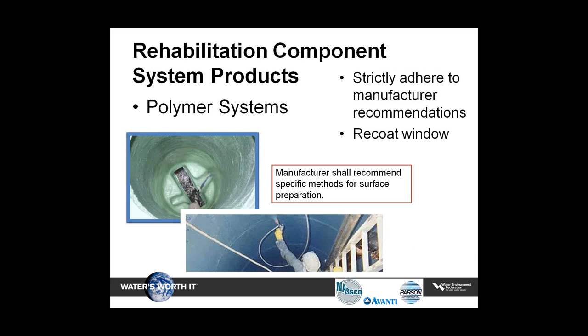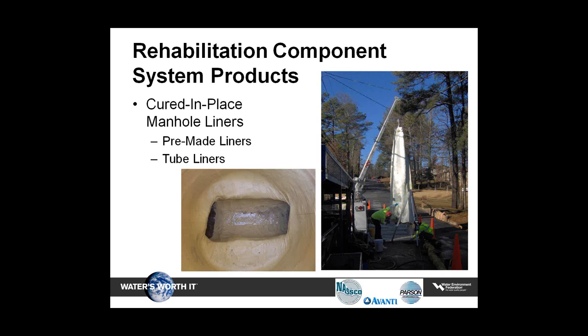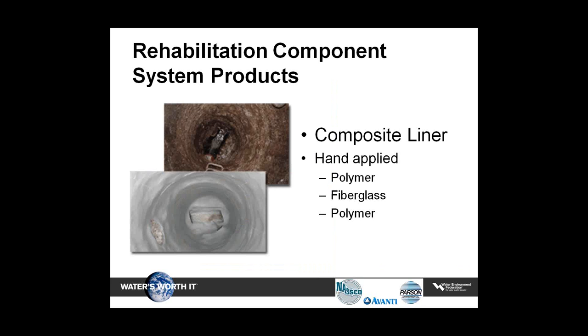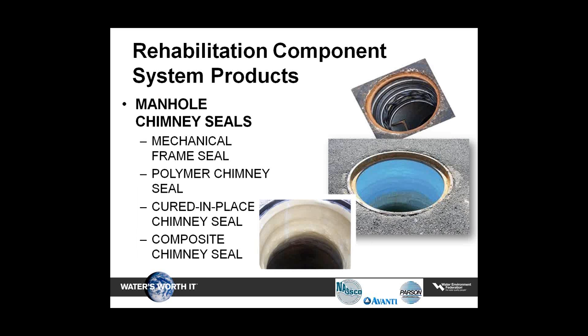For polymer systems, strict adherence to the manufacturer's installation procedures shall be followed. Products may be troweled, sprayed, or spin cast, and manufacturers shall determine the recoat window. Cured-in-place liners can either be pre-made liners or tube liners. Pre-made liners are custom fabricated and can accommodate a variety of manhole shapes and sizes. The tube liner system includes a constant diameter tube that is stretched to fit a range of manhole sizes and lengths. Composite liners shall be a multi-layered composite comprised of layers of epoxy and fiberglass, handcrafted and constructed in place and cured at ambient temperatures, with fiberglass overlapped a minimum of three inches.